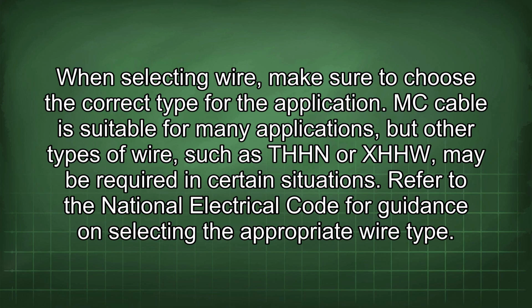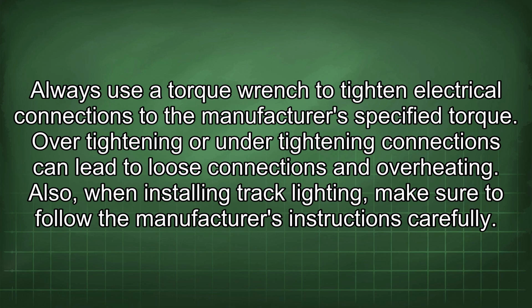When selecting wire, make sure to choose the correct type for the application. MC cable is suitable for many applications, but other types of wire, such as THHN or XHHW, may be required in certain situations. Refer to the National Electrical Code for guidance on selecting the appropriate wire type. Always use a torque wrench to tighten electrical connections to the manufacturer's specified torque. Over-tightening or under-tightening connections can lead to loose connections and overheating.